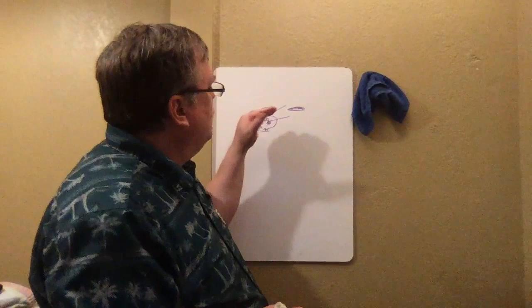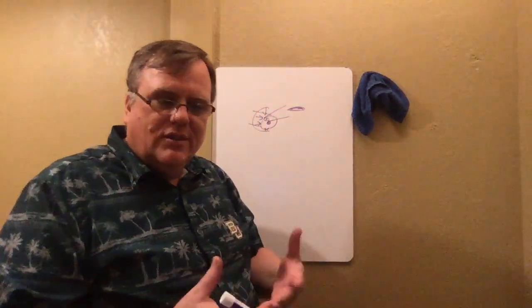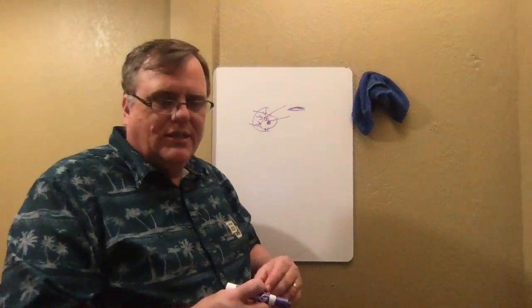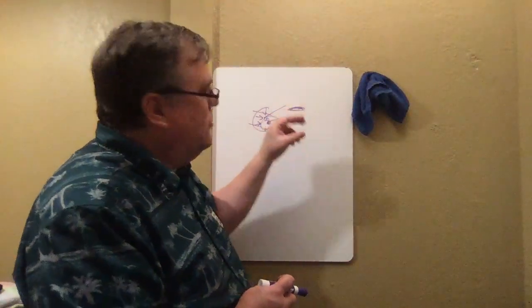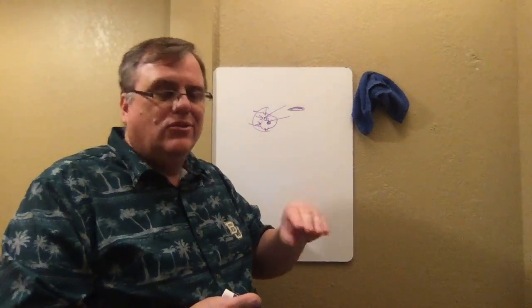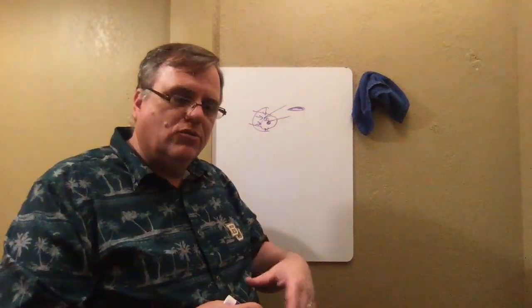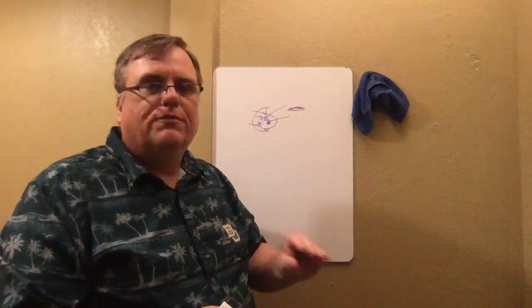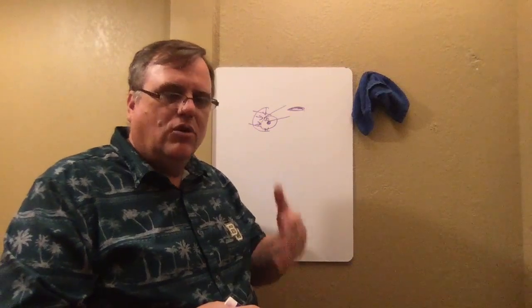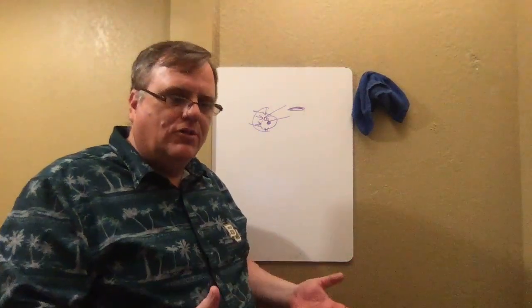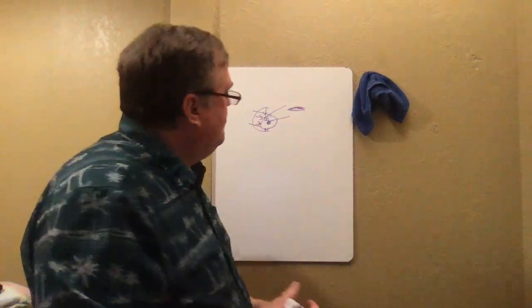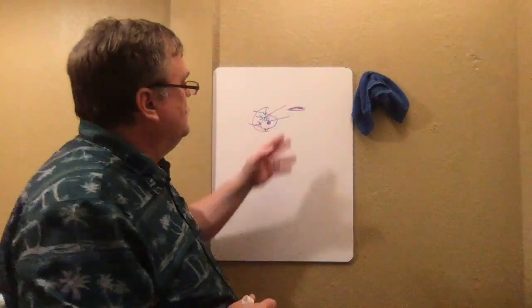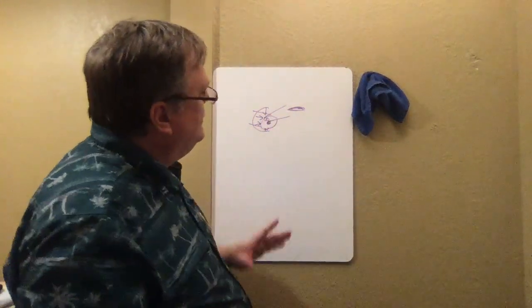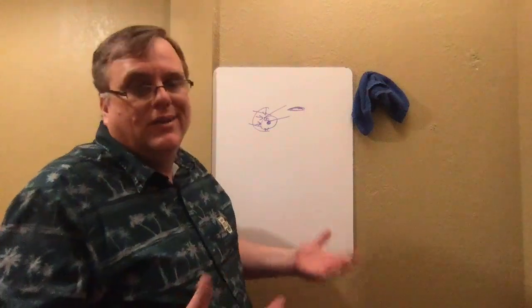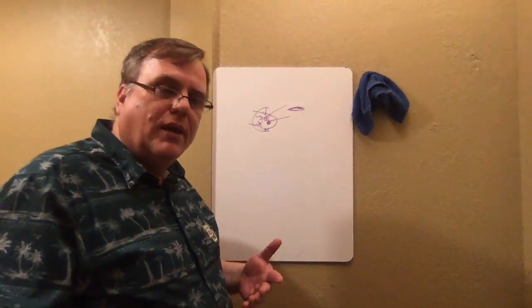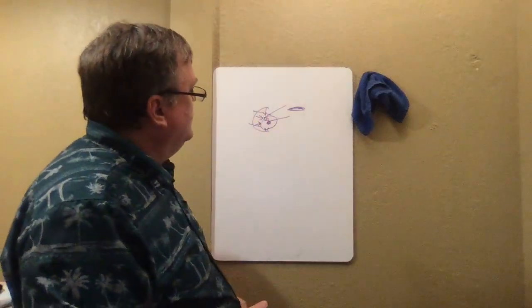Some of this kind of makes sense. Once it's already flowing, it's going to tend to cause you to get a different pressure reading. We want to get the accurate measure of the static pressure when it first opens up, so you don't want any flow in there creating pressure differentials inside the blood vessel. When fluid flows through there, it'll cause a pressure difference as it's flowing, and that pressure difference will mess up your measurement. When it's not flowing already, everything's much better. A lot of studies have been done, and they found out that this is indeed the truth. It just makes sense, particularly for those of you who have had a mechanical engineering background. You can think about fluid flow through pipes, and it works exactly the same.